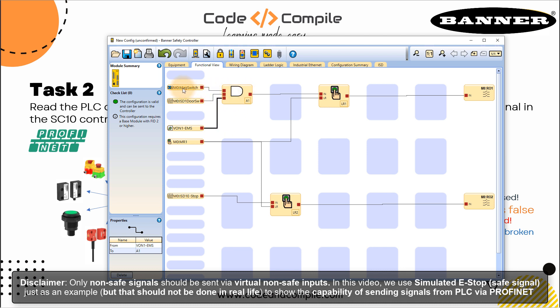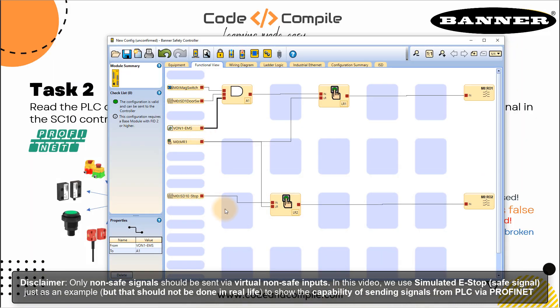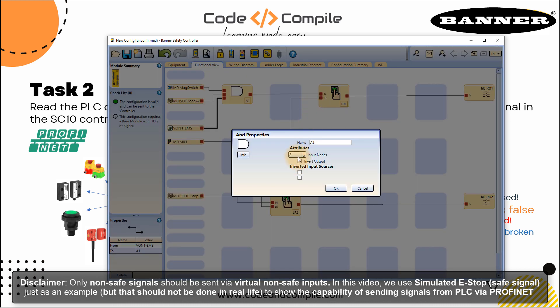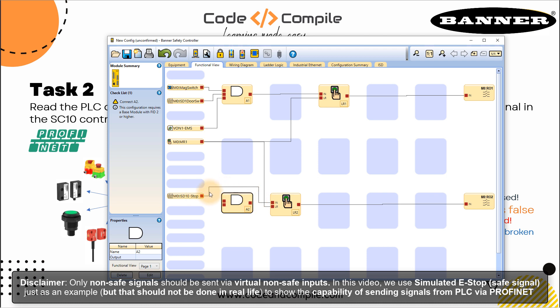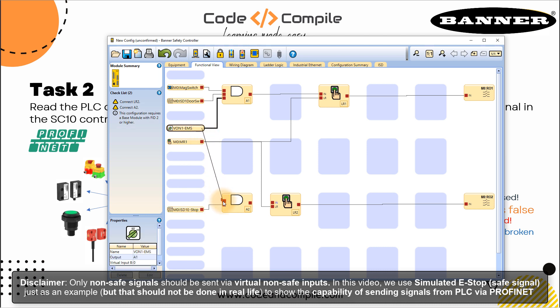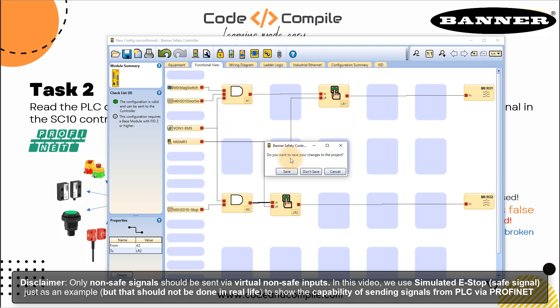So now this is a series block with magnetic switch, door switch, and e-stop coming from my Factory environment. I can also connect it here, but in this case I need an AND block. I will take an AND block of two inputs and click okay. Now this e-stop, which was coming from my safety kit, will go as my input here, and I can also take it here. The output of the AND block will go to my alert block. Now this input is associated with both AND blocks — that's the task. Now we have to download, write it, and save.